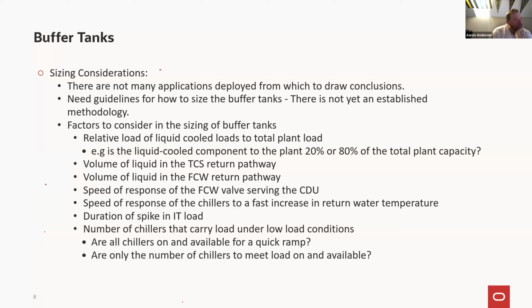Yeah, I would agree with you. Our approach, and obviously we're 90% liquid cooled, it stops making sense if you've got one or two CDUs, maybe, but at scale you put excess thermal capacity in for a lot of reasons. Even chillerless plants, I would argue, you can create ride-through for the thunderstorm that passes through and your evaporative cooling goes to crap for 45 minutes.